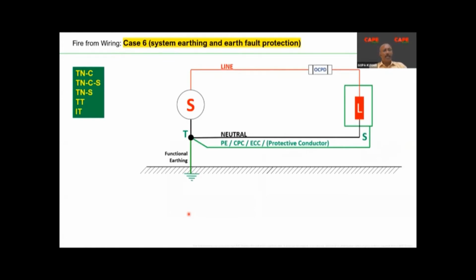Another point is system earthing. Electrical systems are classified into TN-C, TN-C-S, TN-S, TT, IT, different kinds of system earthing. For hospitals, we are supposed to follow a wiring called TN-S. I'm showing a picture: you have a source, you have the OCPD, which stands for an MCB for example, and you have the equipment. The body of the equipment is connected back to the neutral of the source through a protective conductor. A wire is used to connect it back. This is called a TN-S system. In a hospital, we are supposed to use this kind of network.